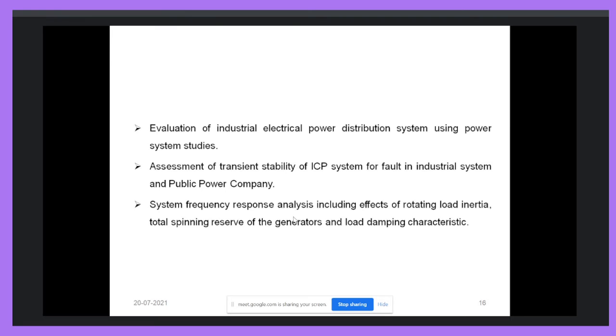We have to perform transient stability analysis also. On the basis of transient stability analysis only, we can design the load shedding technique. The relay based load shedding technique also depends on the stability analysis. We have to create a worst operating scenario and determine the system parameters for that scenario, suppose frequency and voltage. Only then will we be able to decide the setting of the relay. So the system analysis is required.